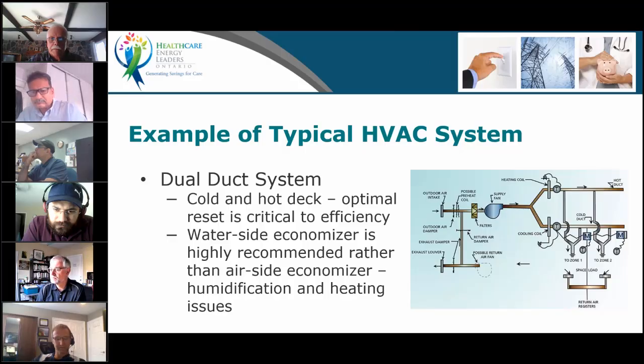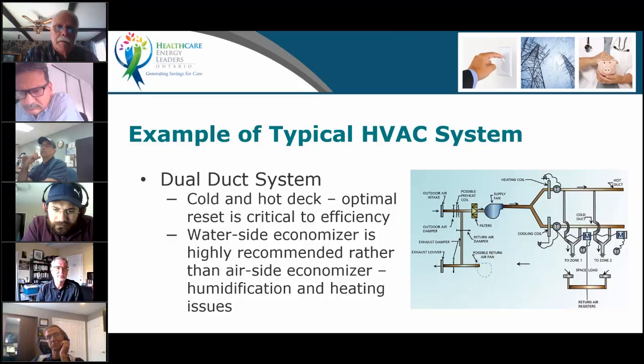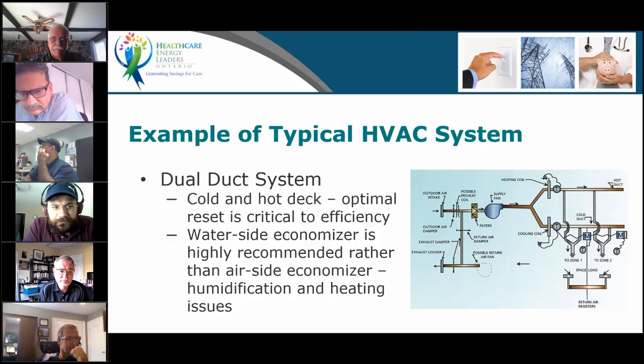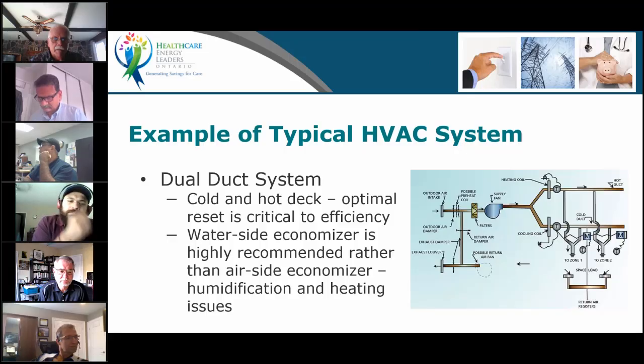So the best way is to have a water side economizer, using your cooling tower to do your free cooling. If you don't have one, it is sometimes worth it to install a plate exchanger and do that kind of free cooling. So again, knowing your HVAC system is critical. Once you know your HVAC system, you also need to know what your air changes are. If you want to meet the CSA standard, do I have my 6 air changes in my office spaces? Do I have my 20 air changes in my operating room? What is my outside air compared to my total air?